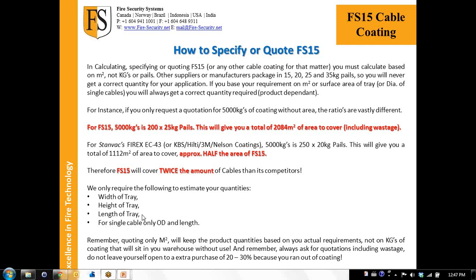As I've stated here, we only require the following to estimate the quantities: width of tray, height of tray, length of tray. For single cables, not in tray, we only need the OD and the length. And for cable bundles? For cable bundles, the same. We would look at that OD situation again.